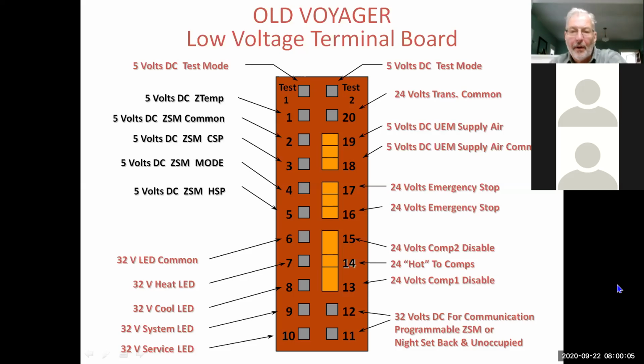All right, so what I've got up here is the old Voyager terminal board. We're going to talk about the test 1 and test 2. And this has been on our units for a long time. A couple things to remember when you're in the test mode is that if the unit runs, it bypasses the communications, but it will never bypass a safety switch.